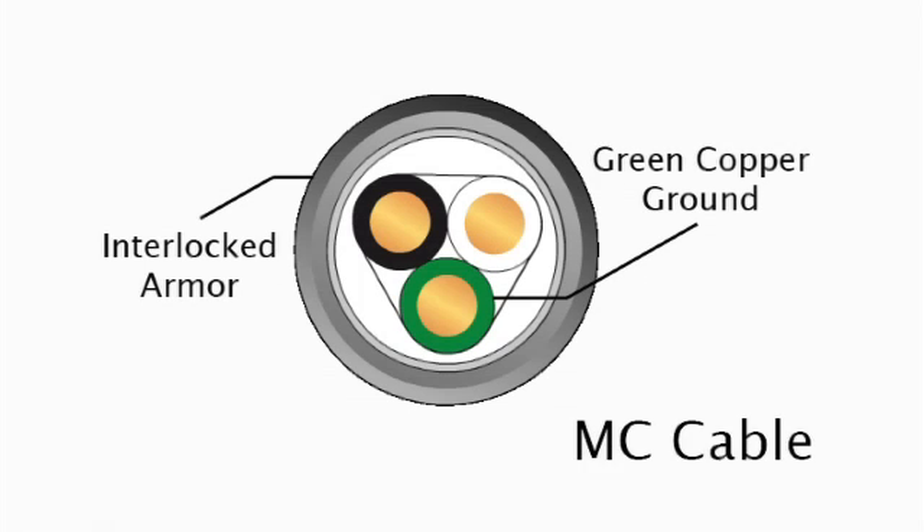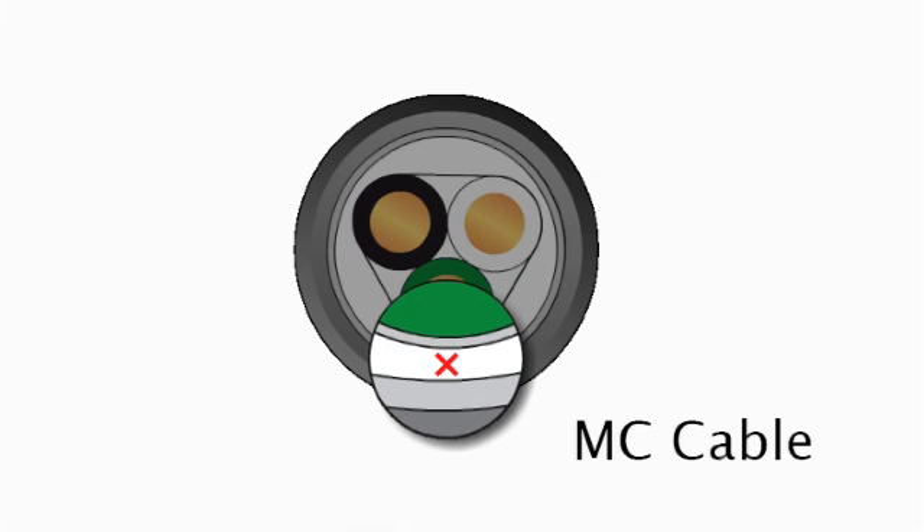The ground path for standard interlocked armor MC is the combination of the interlocked armor and the green copper ground. There is contact between the interlocked armor and the green copper ground throughout the entire cable length.